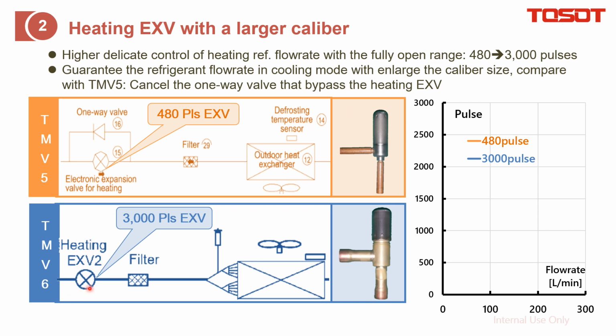The reason is that in cooling mode, especially when the outdoor compressor is in higher frequency, at that area the refrigerant flow rate is extremely high. Even when this is fully open, it is not enough. In other words, the refrigerant is still metering at this location, and that is what we don't need. So we need to create a check valve here to let more refrigerant bypass here or to pass through this area as soon as possible.